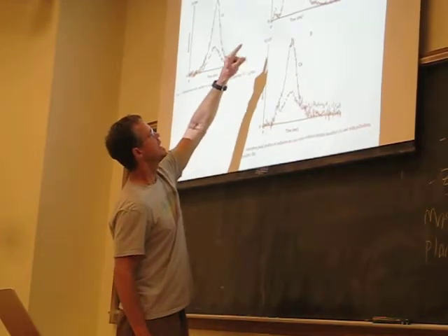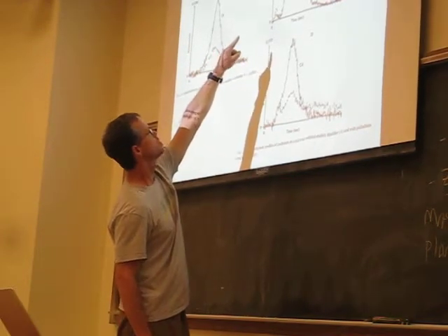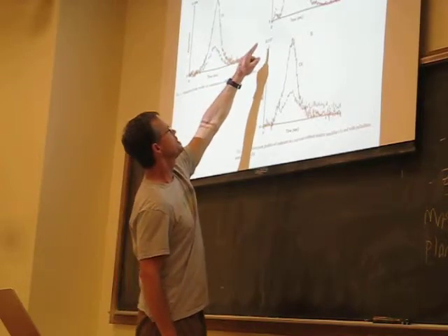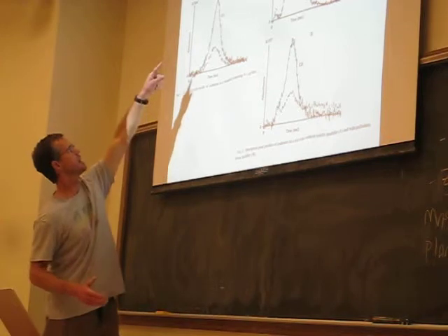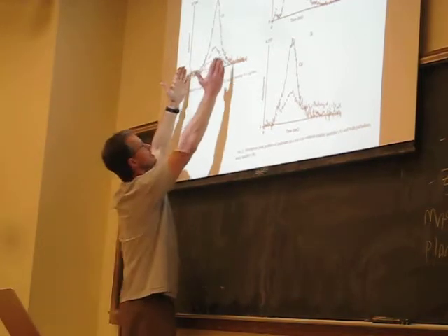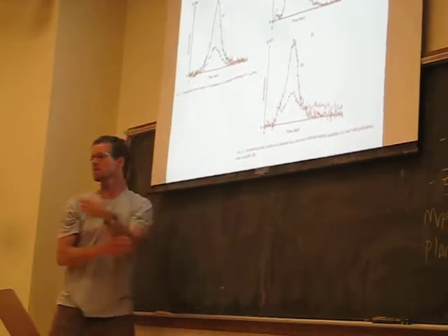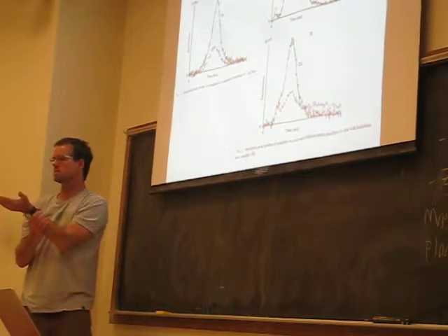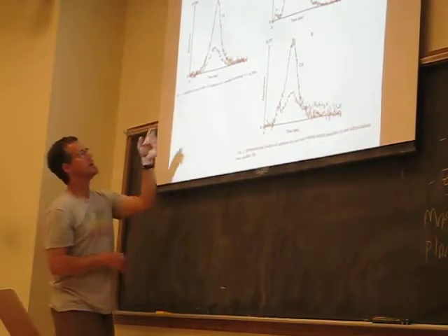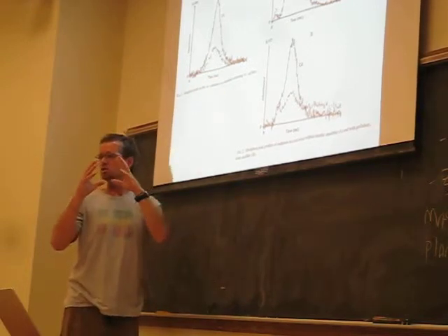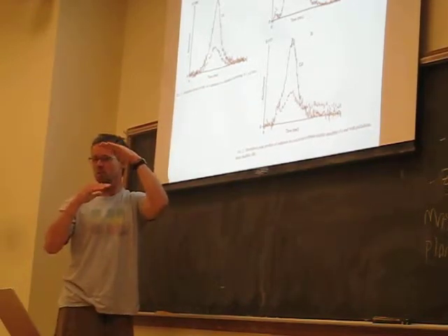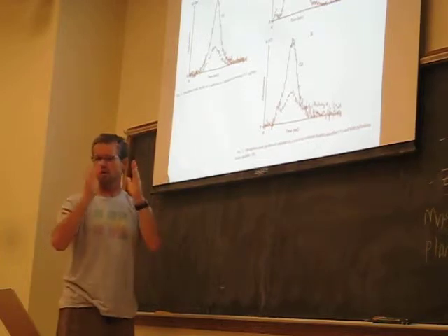Then they look at their sample, a wine sample, which is the one at the top, and you see two things are different. Now, remember, when the instruments are reading here, they're not measuring the height of the peak, they're measuring the integral of the area of these peaks, just like you would do for the ion chromatography experiment. That way, if the peak shape changes, it's not so much an issue as it would be if you were measuring just the total height, because you're measuring the whole area.